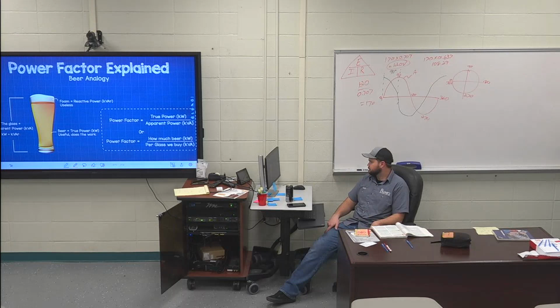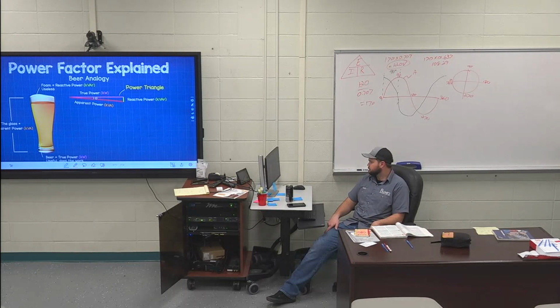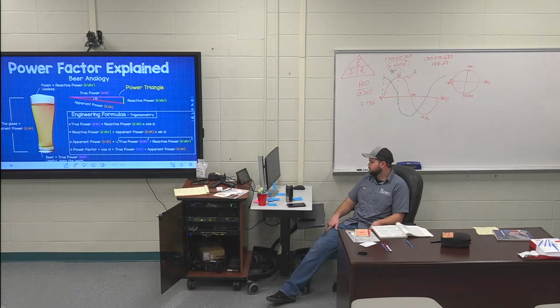So it's telling us how much value for money we're getting for the power we consume. The power factor is expressed as a power triangle, which is easy to visualize. The true power is the adjacent line. Then we have the reactive power on the opposite side. We have the apparent power, which is the hypotenuse. There's an angle from the true power to the apparent power; this angle is known as theta. As reactive power increases, so does the apparent power in kVA. This gives us the power factor triangle, which is just the basics.